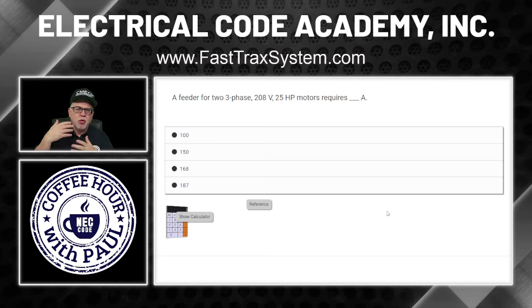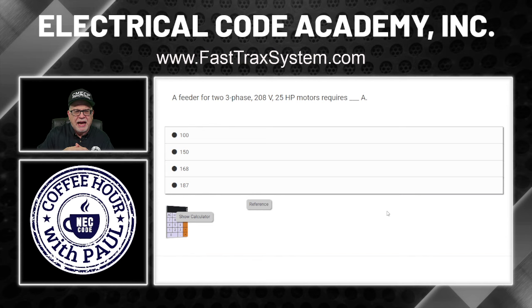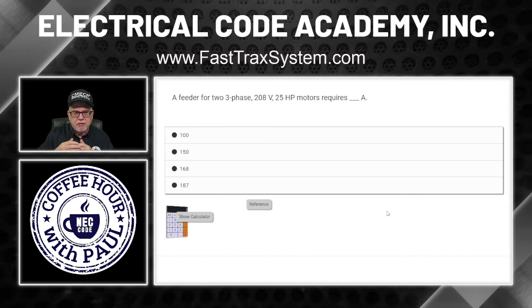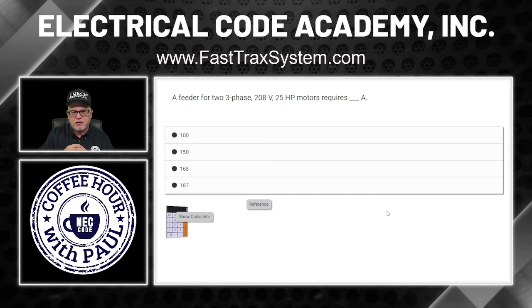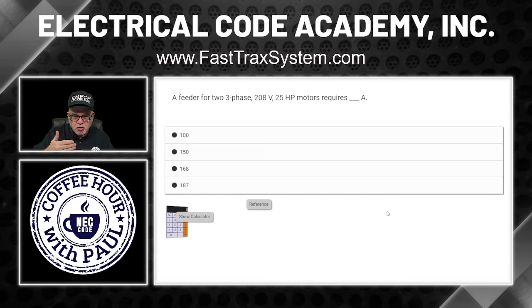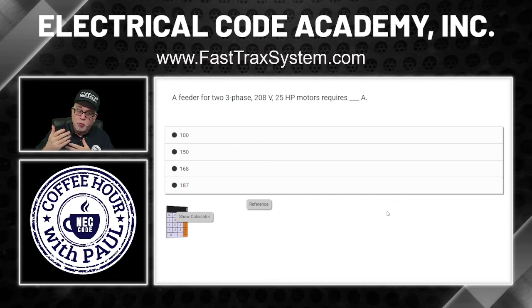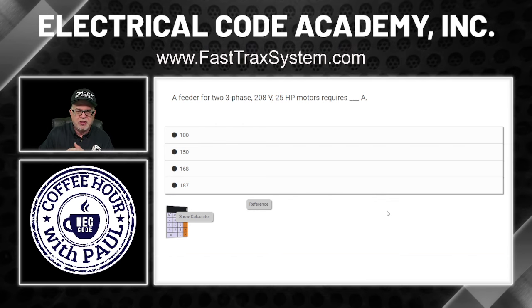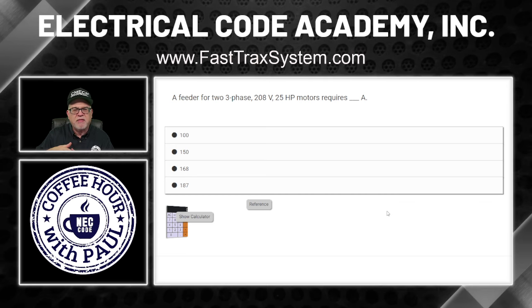So if you do this enough, do it for the tables too. Have one table that says ampacity, 310.16 table. What about equipment grounding conductors, 250.122? What about grounding electrode conductors, 250.66? What about supply side bonding jumpers and grounding conductors minimum sizing, 250.102(C)? So, and if you want to be more specific, the table is C1. All of these things. What about motors? FLCs, 430.248, 430.249, 430.250, 430.247.